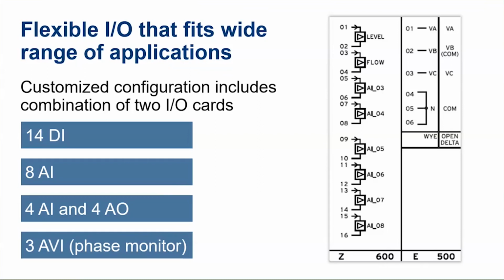This brings in three-phase voltage up to 300 volts AC. Anything higher than that, you can put a PT in front of and get it down to something below that 300 volts, and we can look at that analog voltage signal, sampling it at 4 milliseconds, so 4 times per electrical cycle. Stay tuned, I'm going to show you what that looks like on a page later in this presentation, so you can see what's going on on the power side of this pump controller.